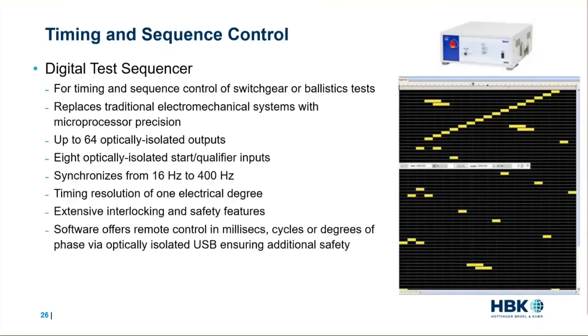Now, a device called a test sequencer is often used to control the operation of a test sequence for switchgear or ballistic tests. This digital test sequencer, shown at the top right, replaces the traditional electromechanical systems with microprocessor precision. In fact, it offers up to 64 optically isolated outputs and 8 optically isolated start qualifier inputs. It's best to have a test sequencer that includes a set of qualifier inputs that will only start a test sequence if all the doors and the switches are properly set, ensuring additional safety to the equipment and the personnel running the test. Now on the right, you can see a sample overview of the software where you can set the timing of every optically isolated output controlling any array of switches during the test.